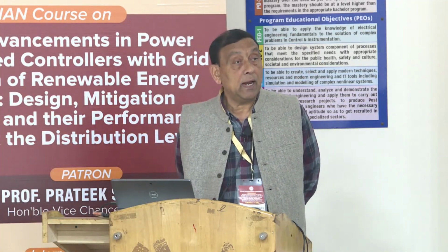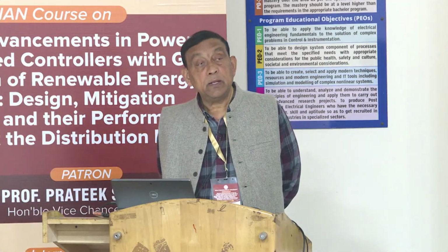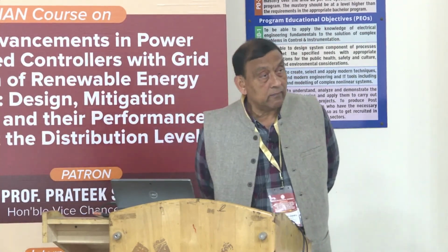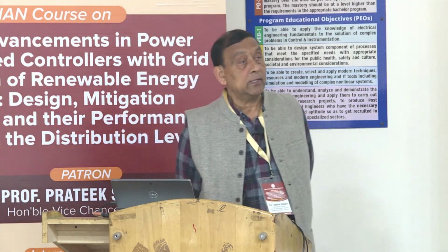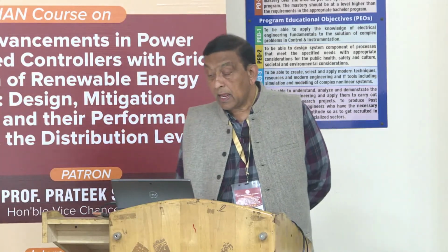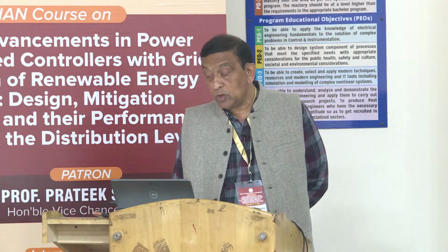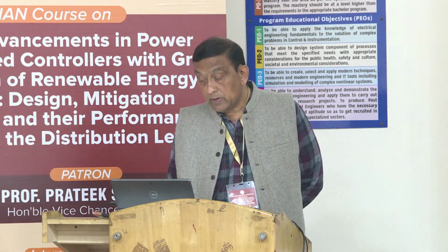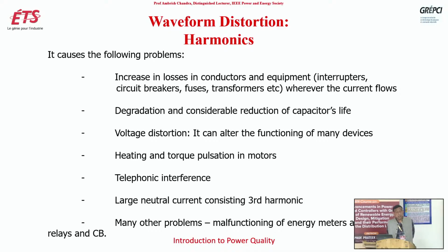Then degradation and considerable reduction of capacitor's life. A capacitor may attract higher harmonics because the reactive impedance in capacitance decreases in value and it may attract higher harmonics. Then voltage distortion, heating and torque pulsation in motors.